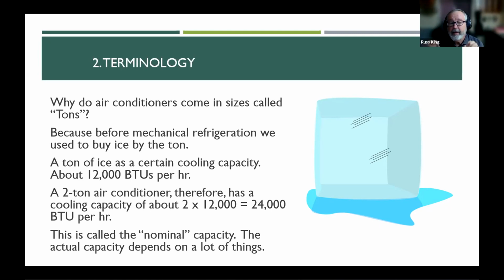The reason we call it the nominal capacity, we're just going to call that unit a 4-ton, we're going to call it a 5-ton, is because the actual cooling capacity, whether it's 12,000 BTUs per ton, might be less than that, or it might be more than that, depending on a whole bunch of factors. The actual design capacity is different depending on a bunch of different things, but we just call it a 4-ton, we call it a 5-ton, okay?